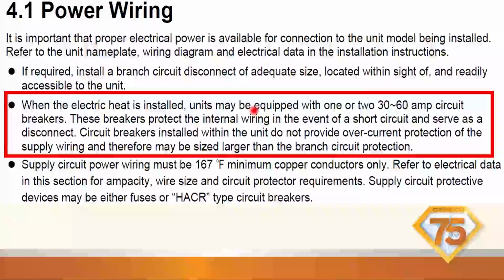But when the electric heat is installed, units may be equipped with one or two 30-60 amp circuit breakers. These breakers protect the internal wiring in the event of a short circuit and serve as a disconnect. So what that's saying is, if it's got two 60 amp circuit breakers on the heat strip, those are just acting as a disconnect, as a switch. They're not actually breaking the circuit if the amps are too high. That needs to be sized correctly through the panel. Circuit breakers installed within the unit do not provide overcurrent protection, so that is not your protection if you have undersized wire to the heat strip. Keep in mind, it is just a disconnecting means.